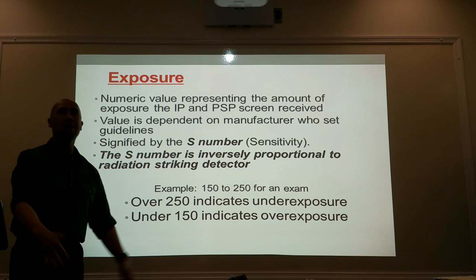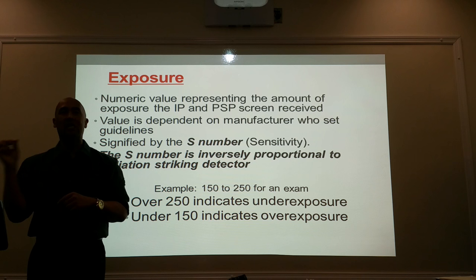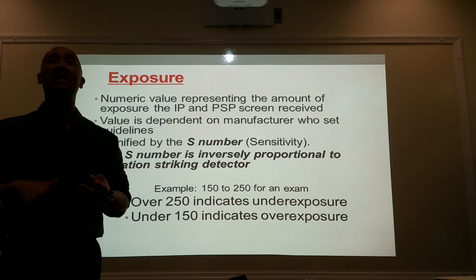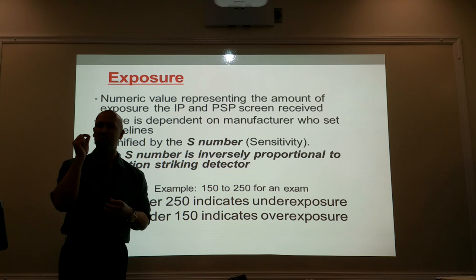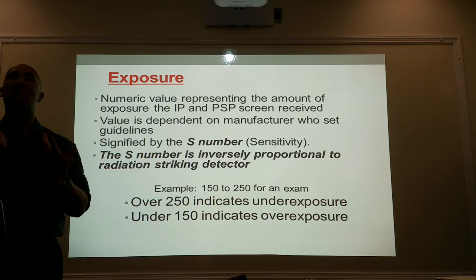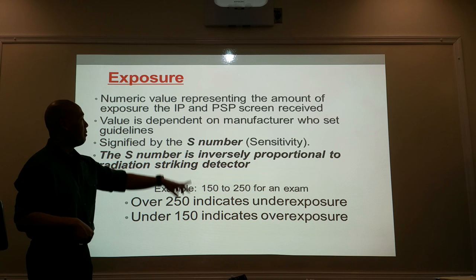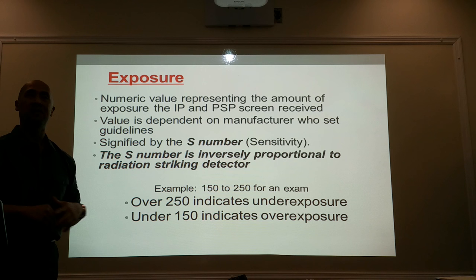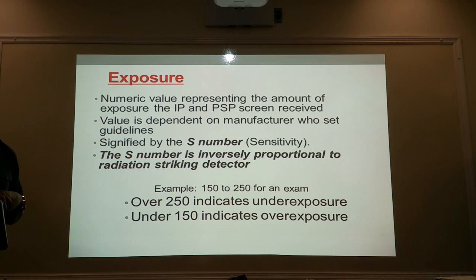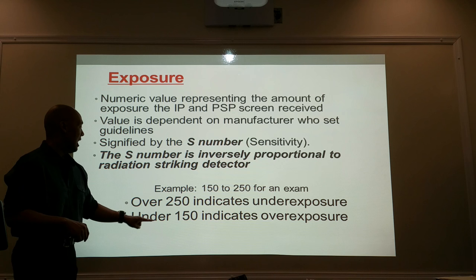When I put my PSP through the reader, not only will it extract the image — because it's the phosphor that stored the amount of x-ray energy coming from the patient, the remnant radiation — but it's also determining the amount of energy stored within those crystals, telling me the quantity of x-rays I used to acquire that image. The S number is inversely related: higher numbers mean your patient was underexposed, lower numbers mean your patient was overexposed. Over 250 indicates underexposure; under 150 indicates overexposure.